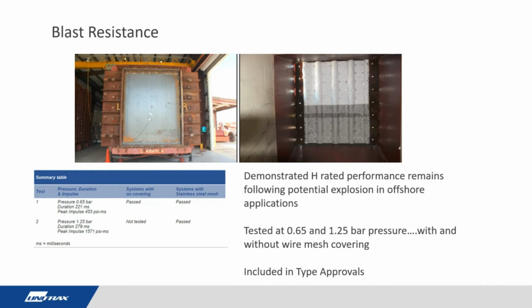After the blast exposure, the test specimens were inspected for damage that would be deemed to affect their fire integrity and performance. Subsequent examination showed the insulation withstood the blast and did not display any significant delamination from the substrate.